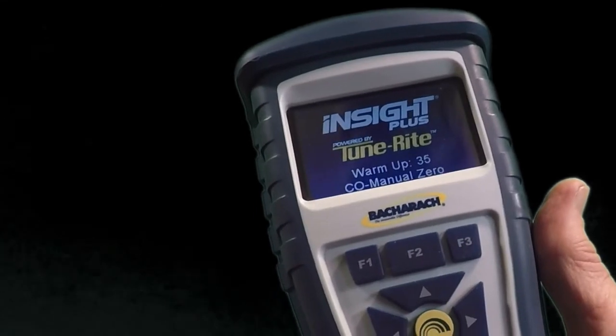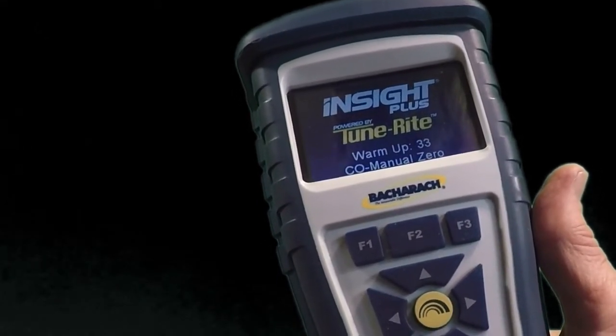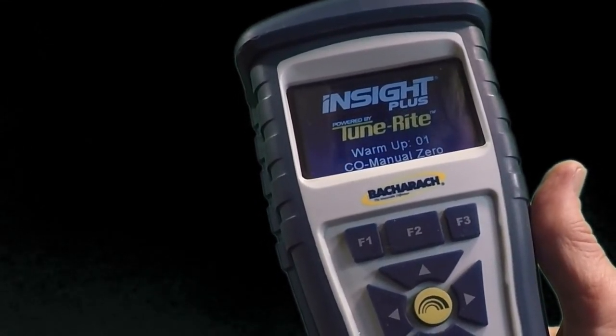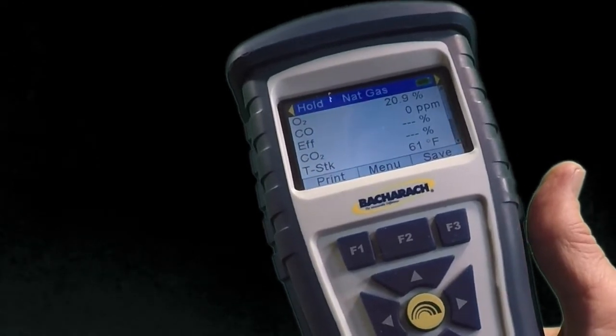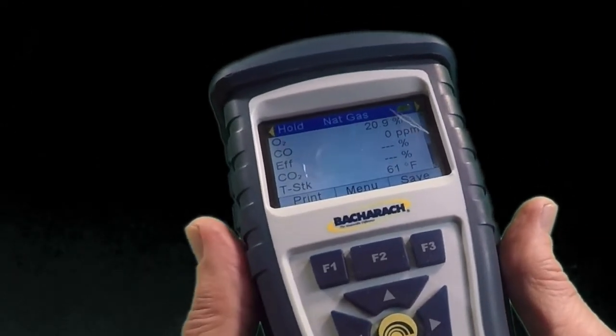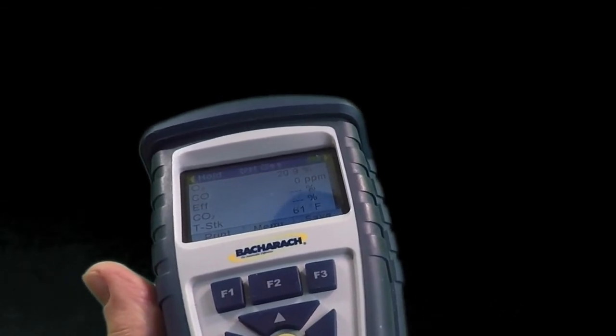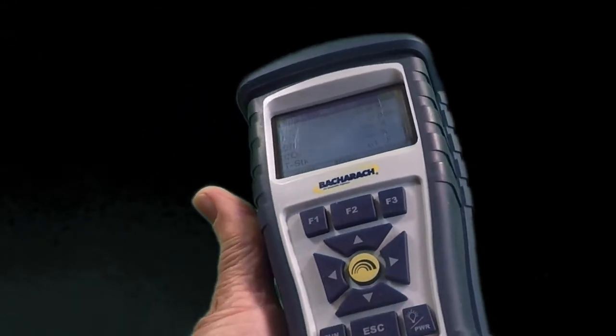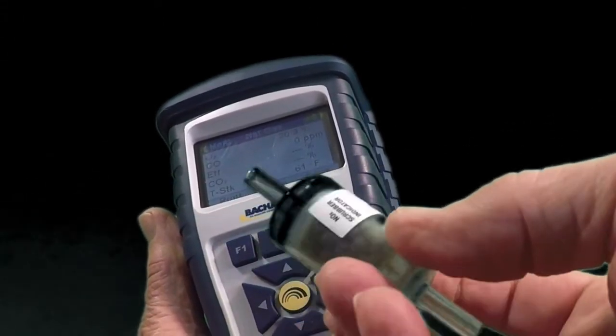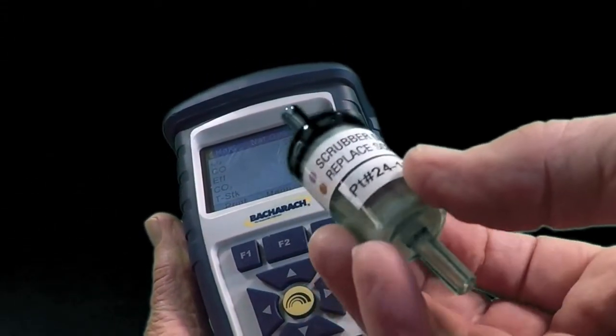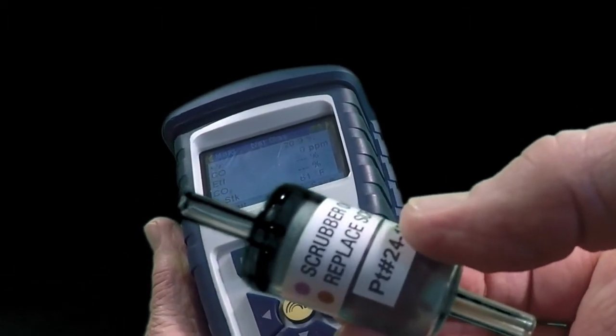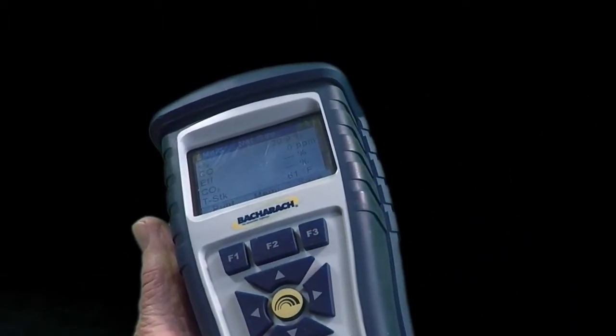Another thing to keep in mind is that all carbon monoxide sensors are cross-sensitive to NOx. One difference between the Intech and the Insight Plus is the CO sensor in the Intech is not NOx filtered. As a result, you'll get more accurate readings with a filtered sensor in the Insight. Bacharach does have an external filter available for the Intech. That's it right here. There's more information on that in the Intech video on our page.